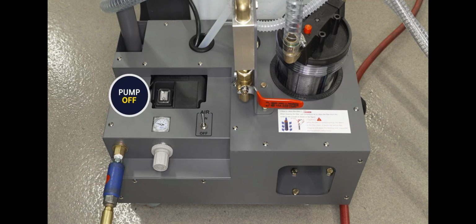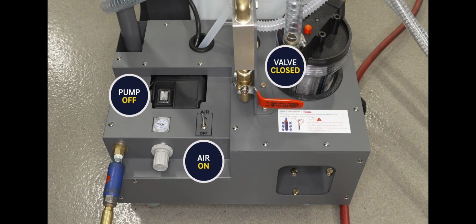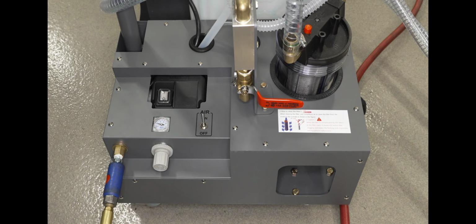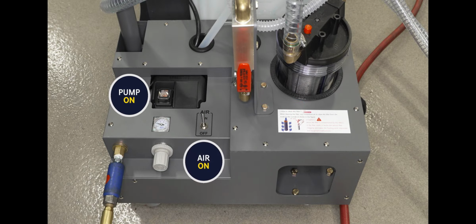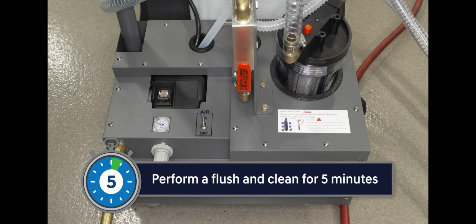Turn the pump off, turn the air supply switch on, and close the inlet valve. After the 2 minutes of air drain, turn the pump on, leave the air supply switch on, and open the inlet valve. This will flush and clean the coolant through the filter. Perform this step for 5 minutes.